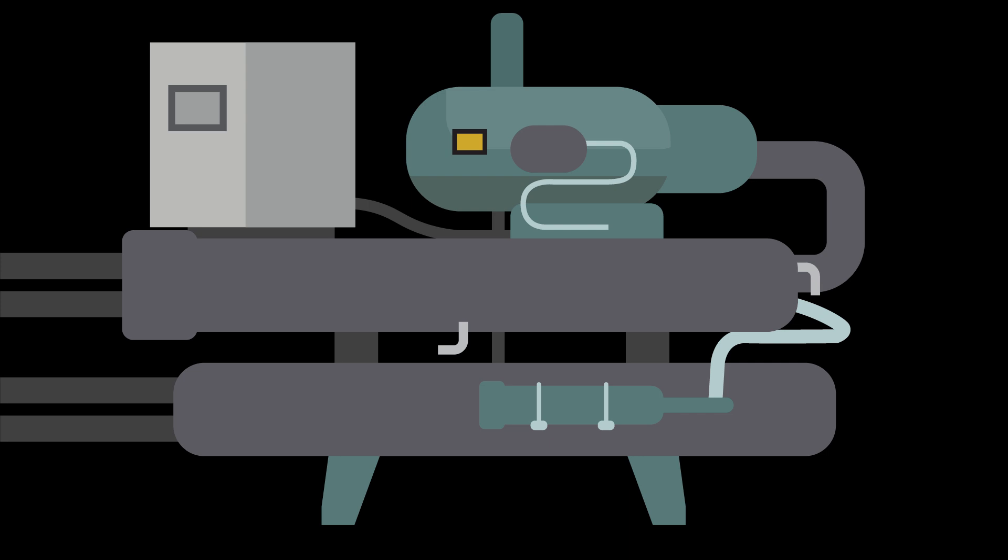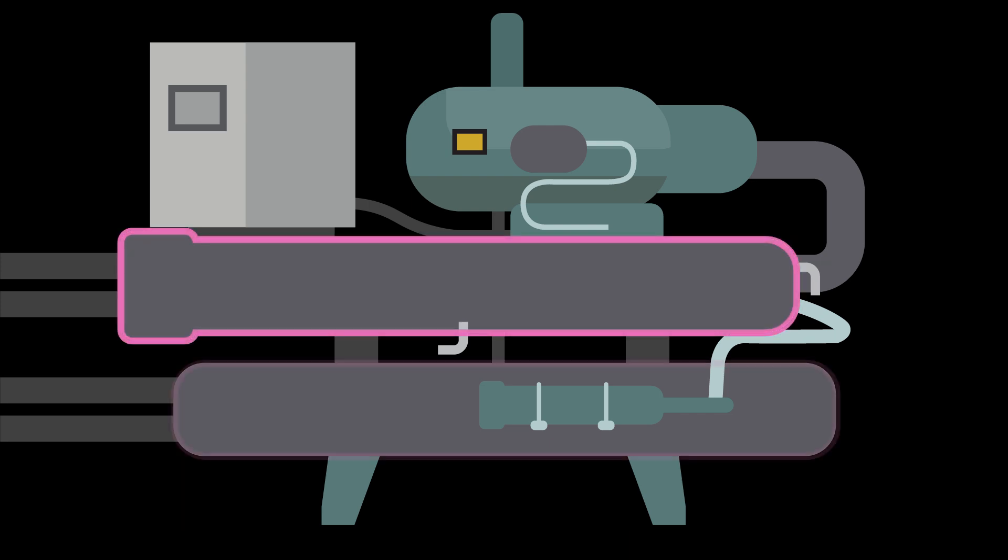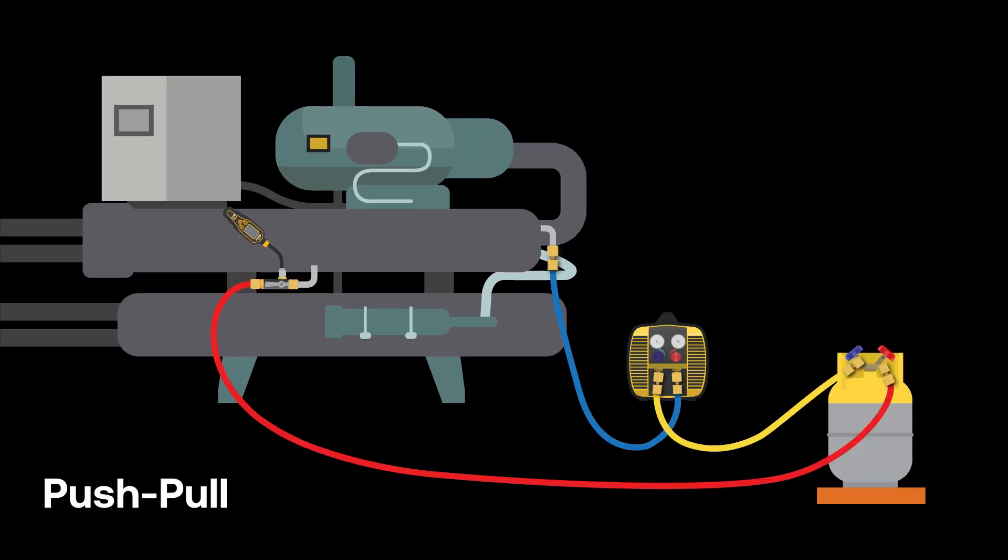When working on systems with a liquid receiver tank, flooded evaporator, or condenser, push-pull recovery can be deployed. This method, while typically a little more complex to set up, can be beneficial as it allows the technician to move large amounts of liquid quickly.